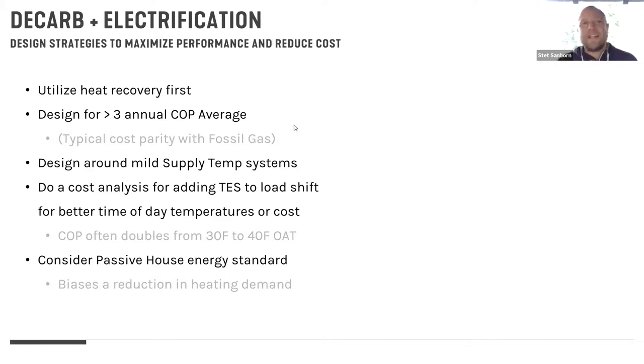If you can, design around mild supply water temperatures. If you're doing a hydronic system, can you heat your building with 120 degree water instead of 180? I know it's crazy. You need different coils if you're doing an air system, but can you get away with low entropy systems like radiant heating? You can heat almost every climate zone with 120 degree water or less with radiant systems. And you can do cooling with radiant as long as you deal with humidity at your DOAS system, with 60 degree water. Those are amazing temperatures to make with a heat pump. Heat pumps love to make mild temperatures, especially when you have a good source energy. Your COPs are going to be just insane.